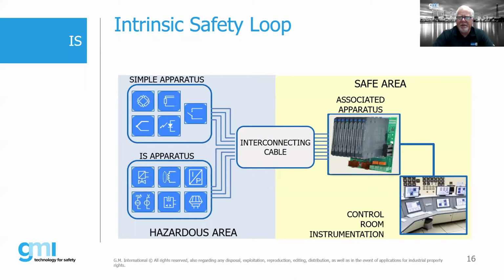Now you'll hear this term a lot, intrinsic safety loop, or in some cases people will call this a descriptive system document or DSD. But intrinsic safety is a system concept, meaning that unlike some of the other EX protection concepts, which are more standalone type protection concepts, it combines the apparatus at the end, the simple apparatus or the intrinsically safe apparatus, the cable, the associated apparatus, and our control circuit. So when we're doing intrinsic safety, we need to understand and match our associated apparatus to the field device, making sure that our cables meet the requirements and that we've taken into account capacitance and inductance with regards to those cables. So we have to match it. It's a system concept. We develop an intrinsic safety loop.